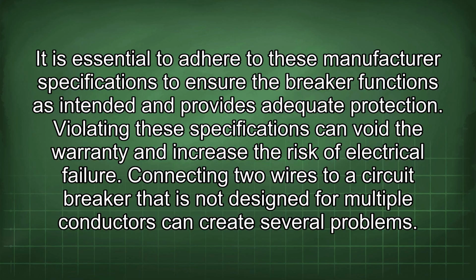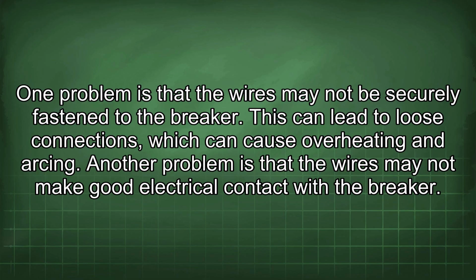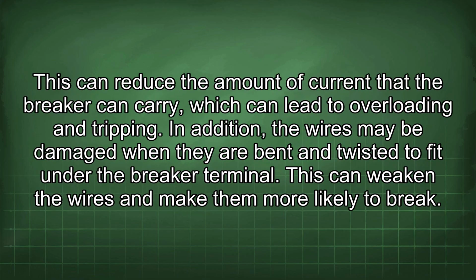Connecting two wires to a circuit breaker that is not designed for multiple conductors can create several problems. One problem is that the wires may not be securely fastened to the breaker. This can lead to loose connections, which can cause overheating and arcing. Another problem is that the wires may not make good electrical contact with the breaker. This can reduce the amount of current that the breaker can carry, which can lead to overloading and tripping. In addition, the wires may be damaged when they are bent and twisted to fit under the breaker terminal. This can weaken the wires and make them more likely to break.